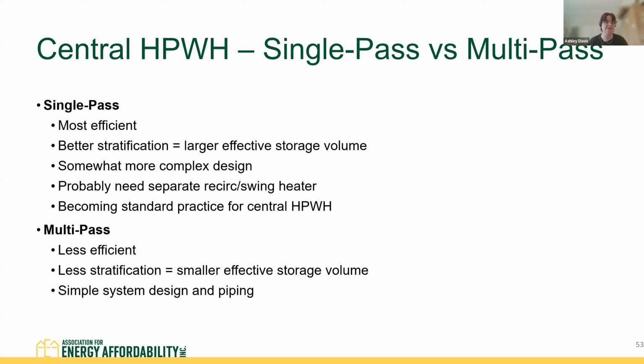There are also multi-pass heat pump water heaters that operate much more like a boiler, where water moves through the unit multiple times in smaller temperature lifts. But these are a little less efficient. Your tank ends up less stratified, but they are simpler, much more like piping a boiler would be. Next slide.